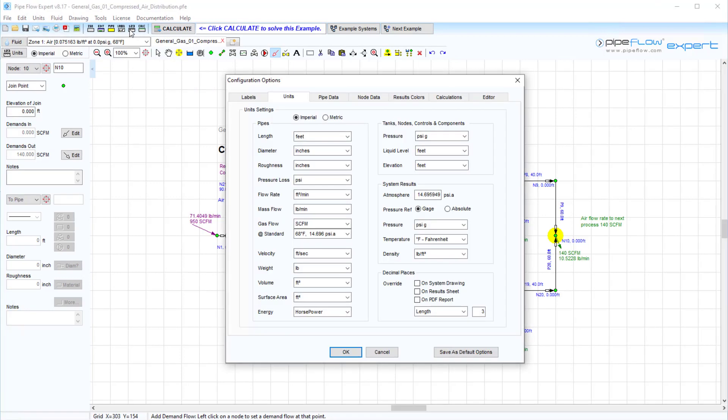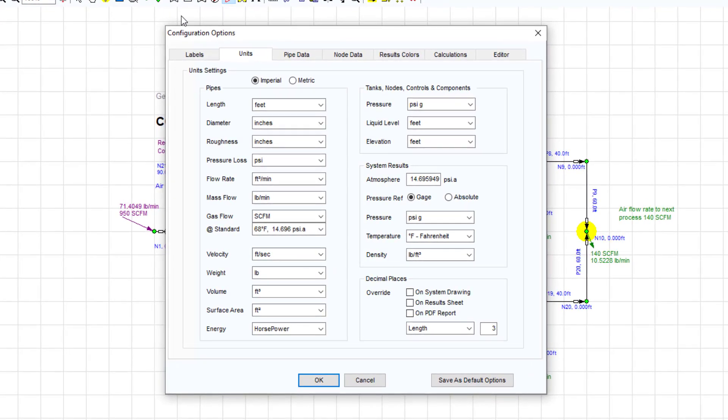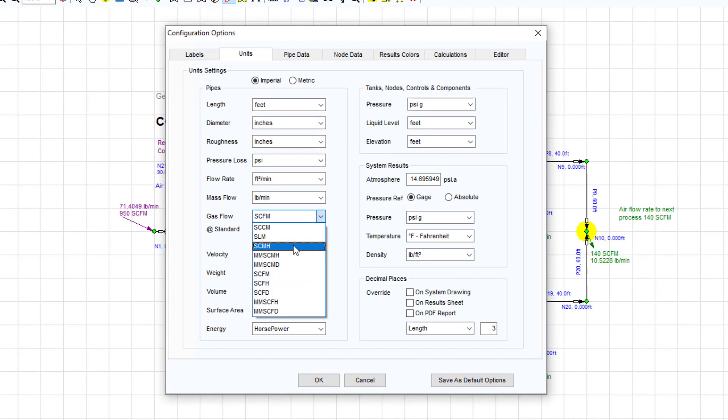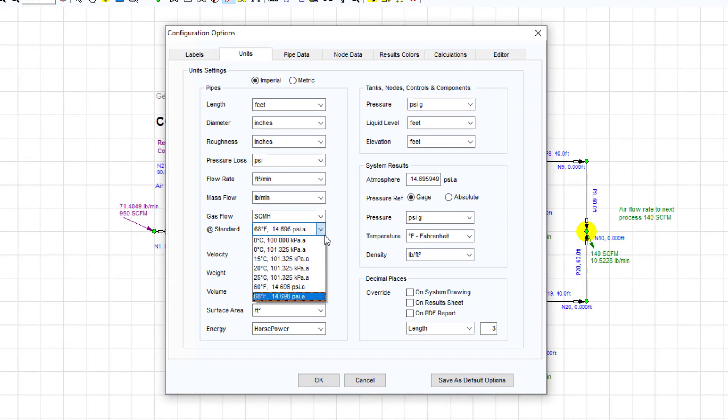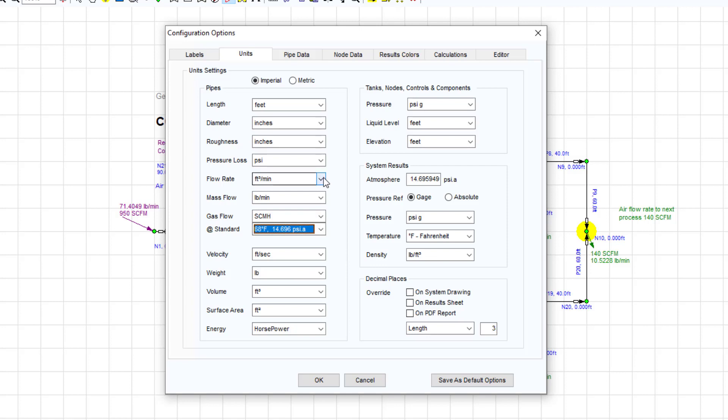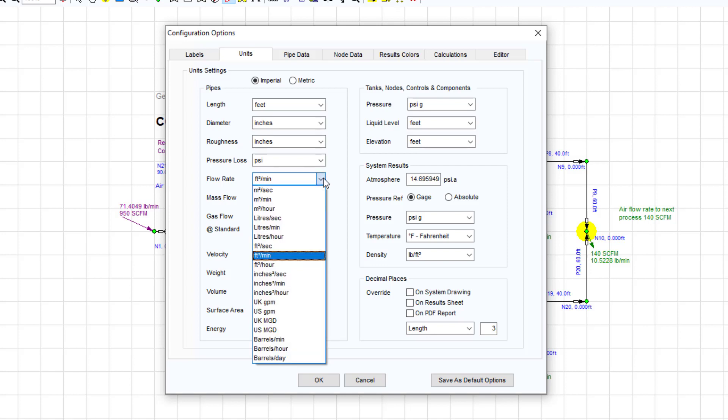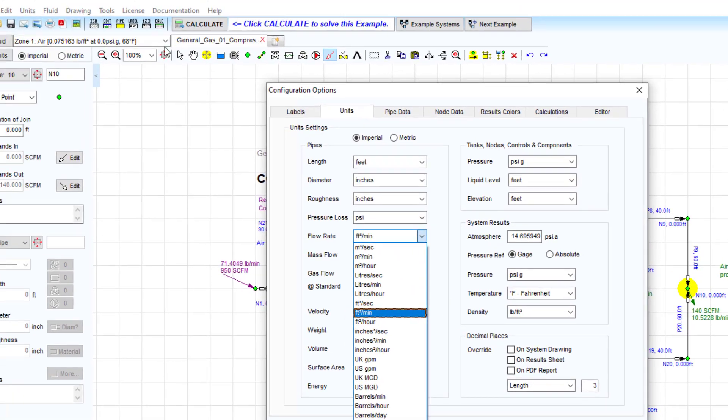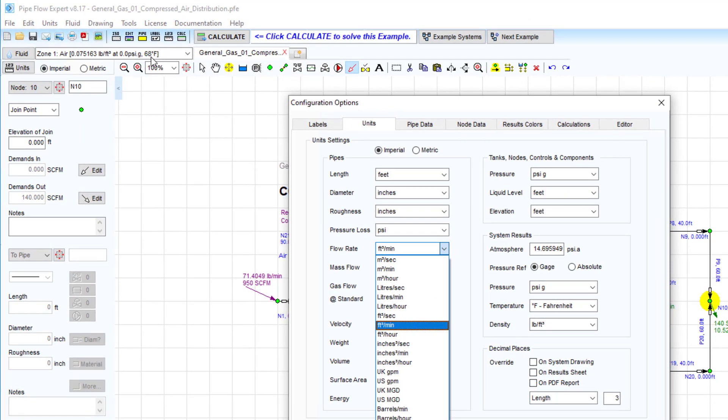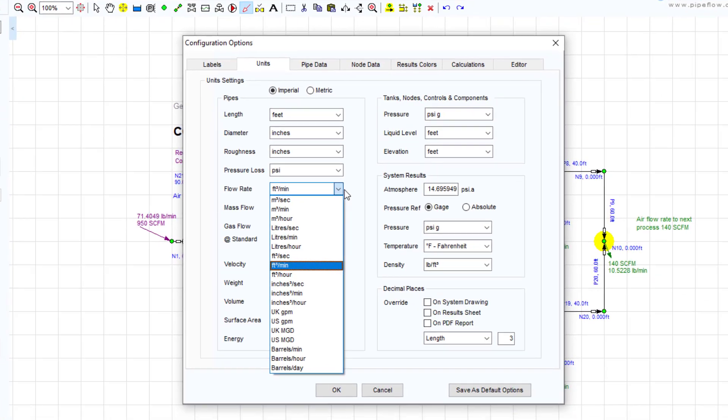Gas flow units such as standard cubic meters per hour refer to the volume of gas at standard conditions for some normal pressure and temperature reference, whereas volumetric flow units like meters cubed per hour refer to the actual volume of gas at the density specified in the fluid data. The fluid data may have been defined for some pressurized condition at a specific temperature.